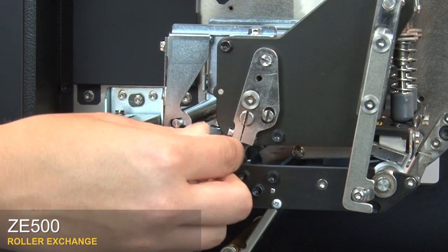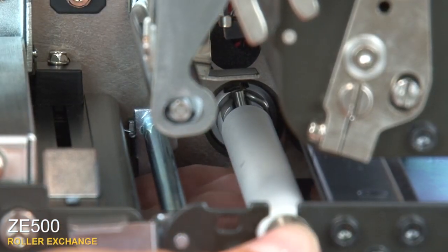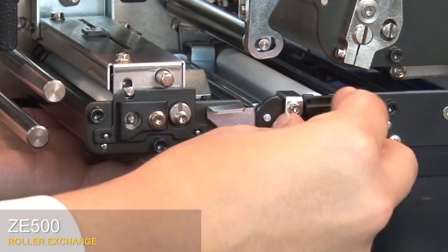Pull the roller forward and lift it out. Align the pin at the end of the new peel roller with the slot in the coupler. Press the roller until you hear it click into place. Insert the tab into the mainframe slot.